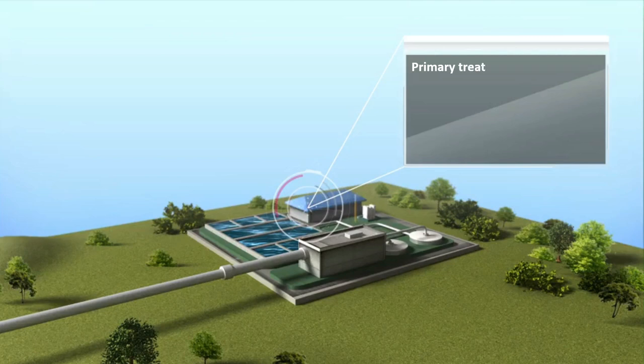Primary treatment slows down the wastewater in a clarifier settling tank to isolate solids that sink or float due to buoyancy. Clarifiers are huge tanks which provide enough retention time for the separation of bigger particles in wastewater. The scum and settled sludge are removed by scraper mechanisms.